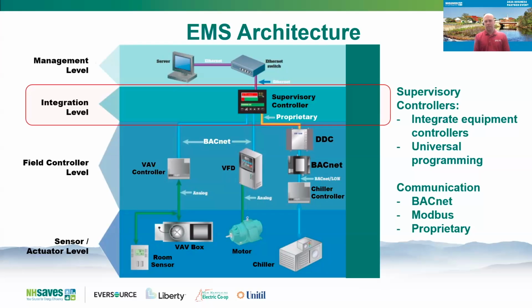And there's a lot of discussion in the market about open systems. And one thing I want to stress, I'm not going to go into it in too much detail, is that there's no such thing as a fully open system. Even if you have BACnet and all of your equipment is talking English, well, the reality is you could have different manufacturers or different people that are in your building, and you can't just change out the people or the equipment.